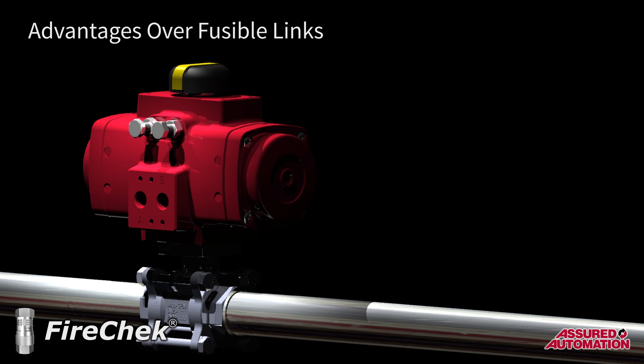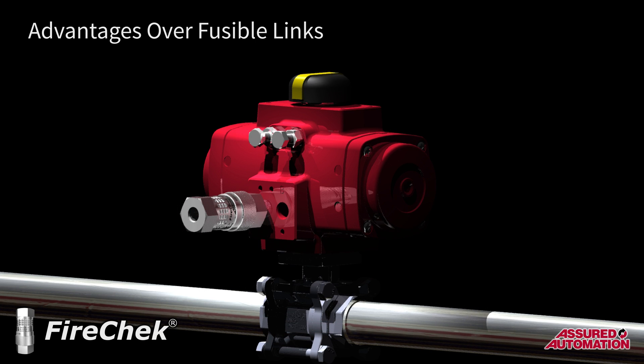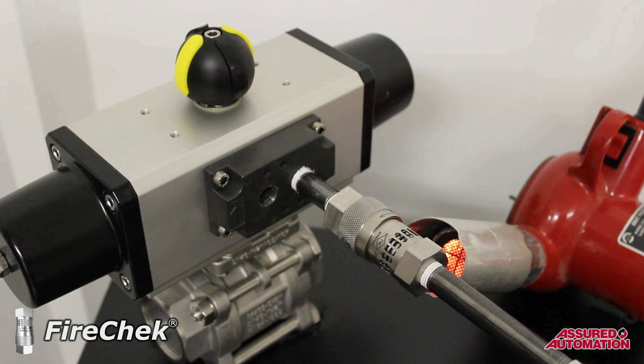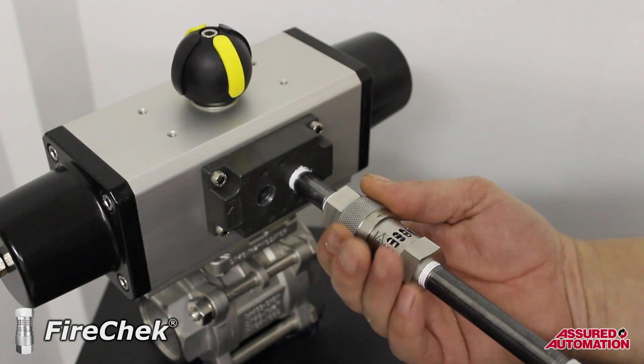Fusible links are another common emergency shut-off technique; however, they require an entire valve assembly dedicated to this function. FireChek valves enable any pneumatically operated valve to perform this duty while maintaining its original functionality, whether it is on-off or modulating. Another valuable feature of the FireChek valve is that it can be tested and reset easily as part of a regular safety monitoring and maintenance program.